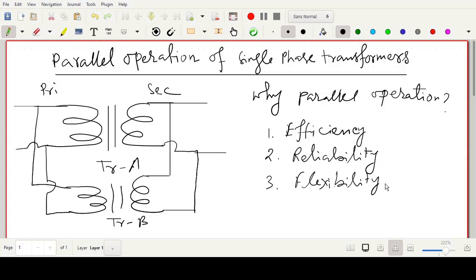Now, three or four things you must remember to operate these transformers in parallel. Number one, their instantaneous polarity should be the same. This is the most necessary condition. And the other three conditions are that voltage rating and voltage ratio must be the same, per unit impedance of the transformers must be equal, as well as the reactance to resistance ratio must be the same. Let us move to page 2.